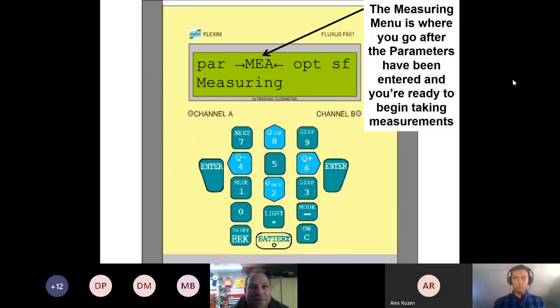Also, it can help you diagnose air in the pipe. If you see that the sound speed kind of jumps from where it's supposed to be to 2000 and back and forth like it's ramping, and you go and look at your signal strength screen, you'll actually see that ramping up and down like a bass on an amplifier. And what that is, is slugs of air. So someone has to go and get the pipe rid of that air.